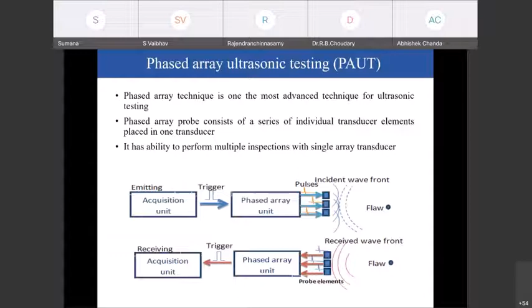Individual elements in which the ultrasonic wave or the small wavefront can be time delayed and synchronized in phase or in amplitude in such a way as it creates different modes of beam. Like you can see here, for example, two wavefronts are generated here. So you will get in phase in this green color position. If we increase the number of elements or the number of wavefronts, you will get different in-phase combinations. So you can get the beam focusing nature.